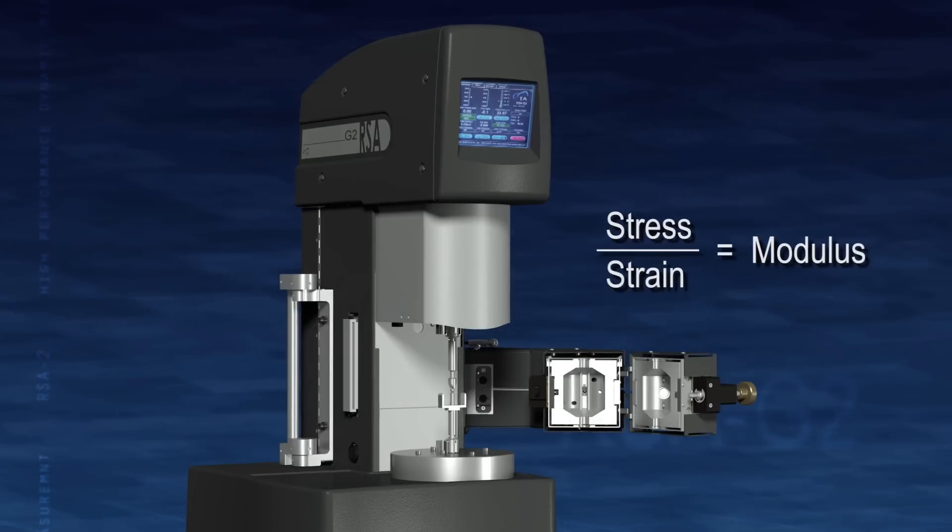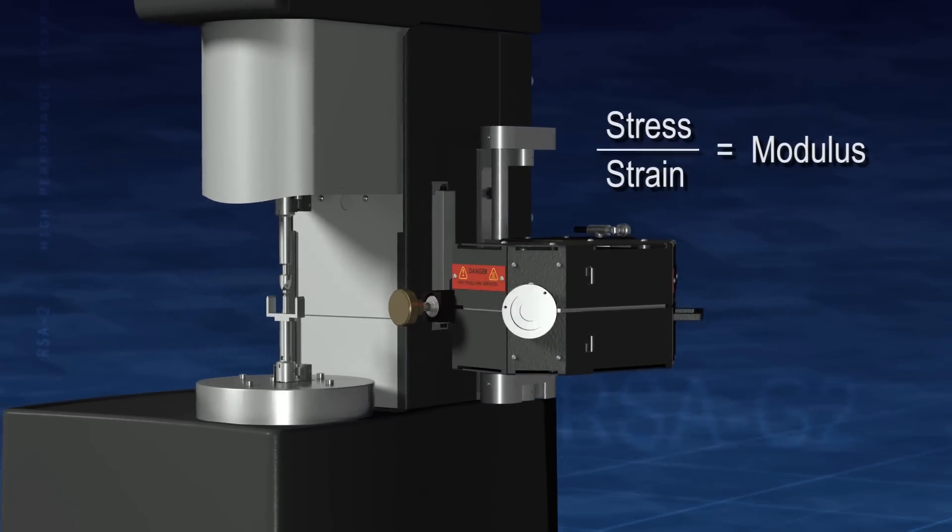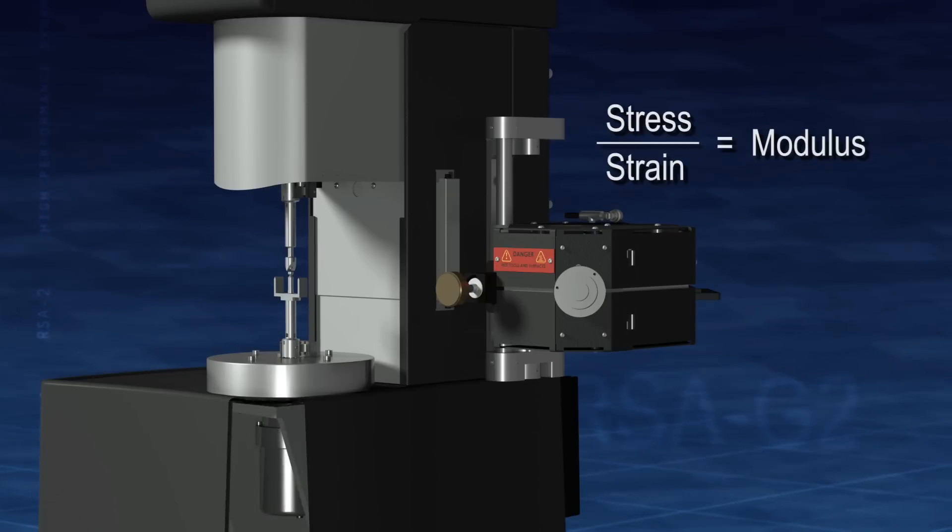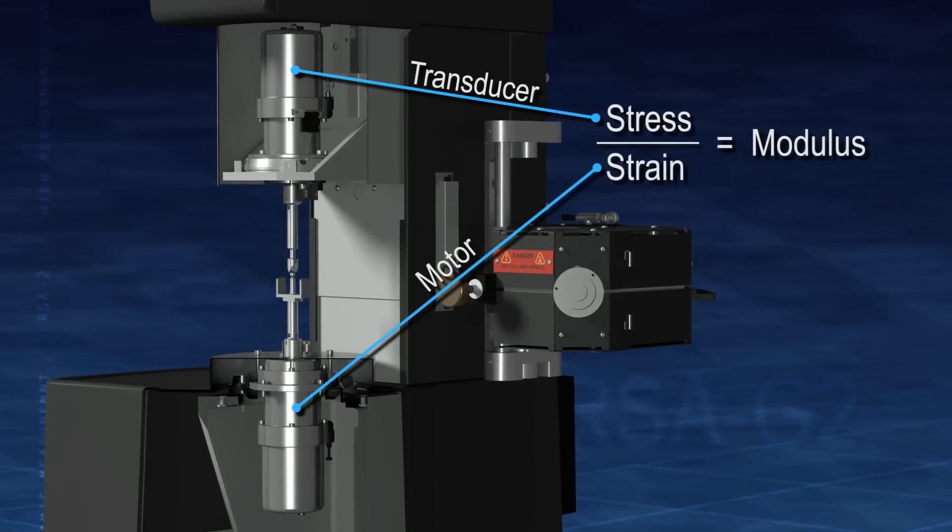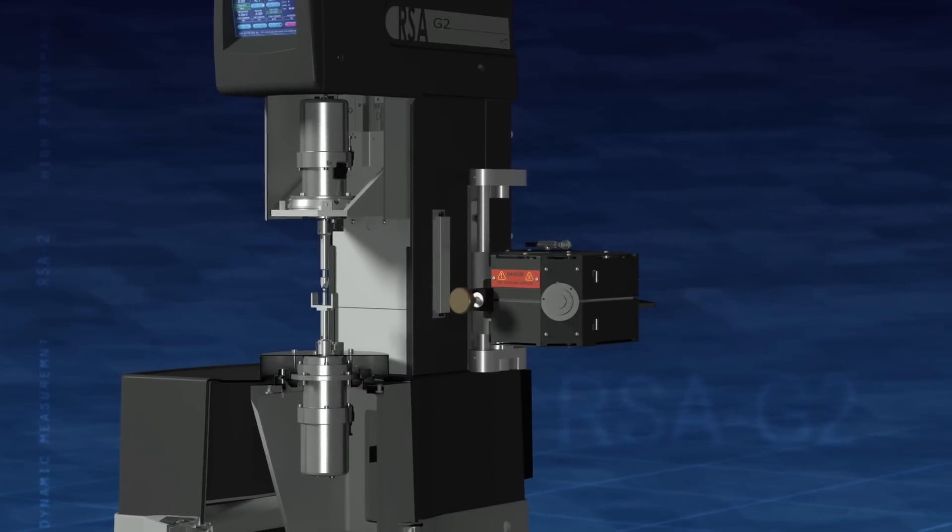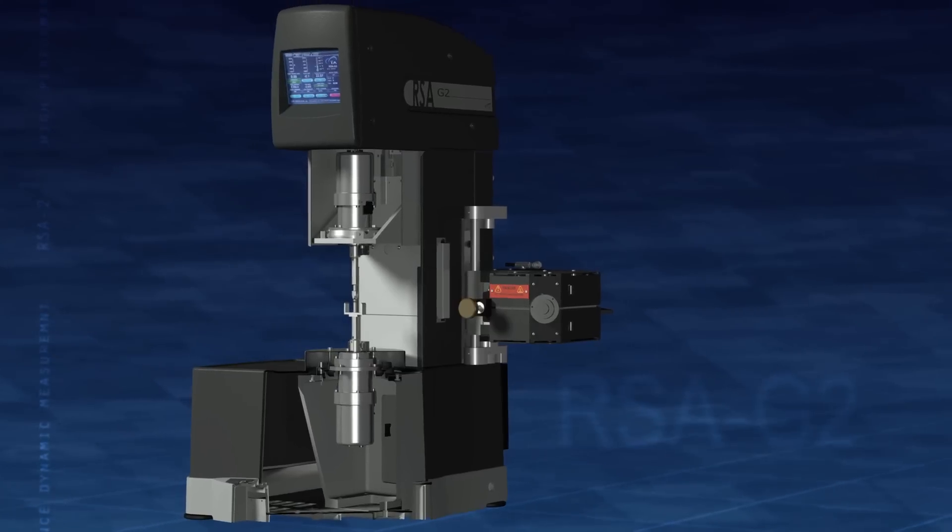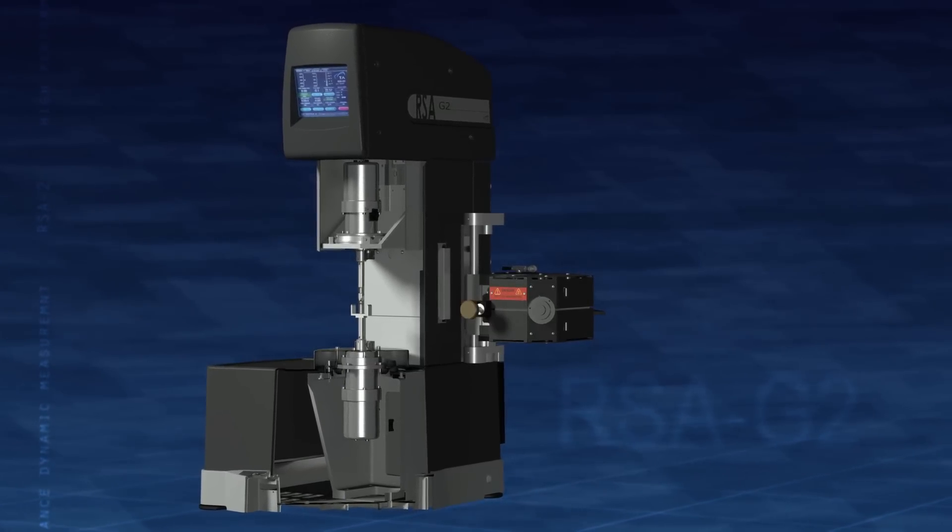The RSA-G2 provides the purest and most accurate viscoelastic information by measuring the fundamental parameters of stress and strain independently. This ensures measurements are free of instrument artifacts such as motor friction and inertia over wide ranges of stress, strain, and frequency.